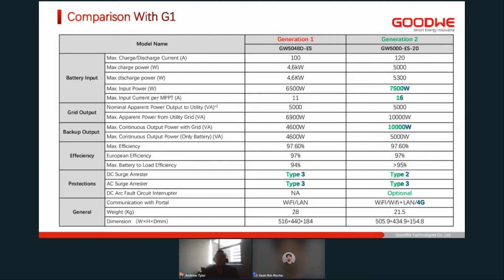So if you look at the comparison, we've highlighted a few important features. The first would be looking at the maximum DC input power. You'll note that on the previous generation, it was about 1.3 or 130% DC oversizing. On the generation 2, we've got 150% or 1.5 DC to AC ratio. So that means that for 5 kilowatts, you can connect up to 7.5 kilowatts of PV panels. That is something we'll discuss later on as a feature, and exactly how it works or how it's applied.